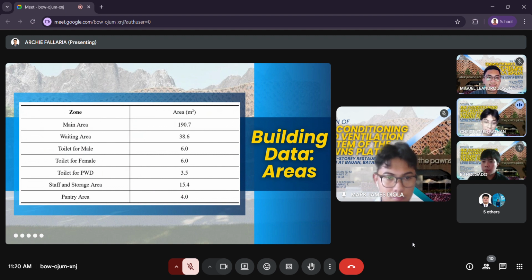The remaining areas, including the toilet for male with an area of 6 square meters, the toilet for female also with 6 square meters, the toilet for PWD with an area of 3.5 square meters, the staff and storage area with an area of 15.4 square meters, and lastly, the pantry area, which has an area of 4 square meters, are supplied with fresh air by the dedicated outdoor air system or DOAS to maintain indoor air quality.